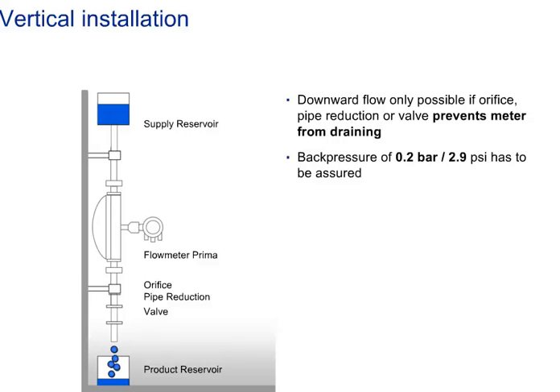In case of higher viscosities or very high flow speeds, the back pressure should be 1.5 times the pressure drop of the meter.